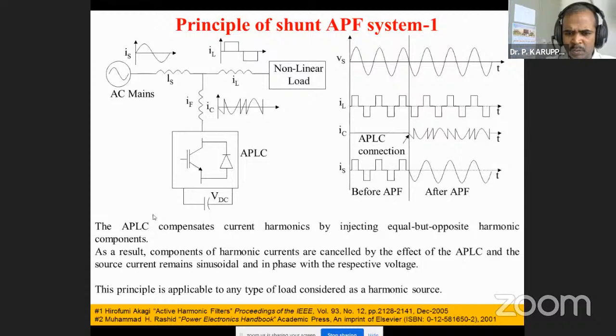Now you can see the currents. This is IS before the active power filter or active power line conditioner. If there is no active power line conditioner, then the source current is also dominated by the load current, which becomes non-sinusoidal. This is the big problem. So you can see from here, if the APLC is not connected, almost IL is equal to IS. That means this will affect the other customers' load. That's why we need to connect an active power filter at the point of common coupling.